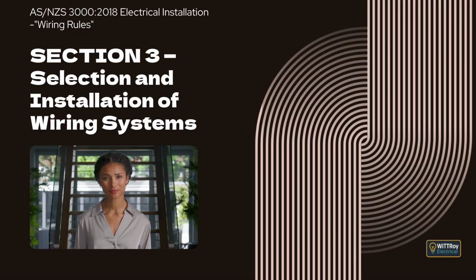Clause 3.11.2 Classification of wiring systems. This clause explains that underground wiring systems are classified into 3 categories, and that the category depends on the type of cable used and the form of enclosure or protection provided. Category A systems are those that are inherently suitable for underground installation and do not require additional mechanical protection. Category B systems are suitable for underground installation only when extra mechanical protection is provided. Category C systems are those where cables are installed in a channel cut into rock and then covered with concrete.